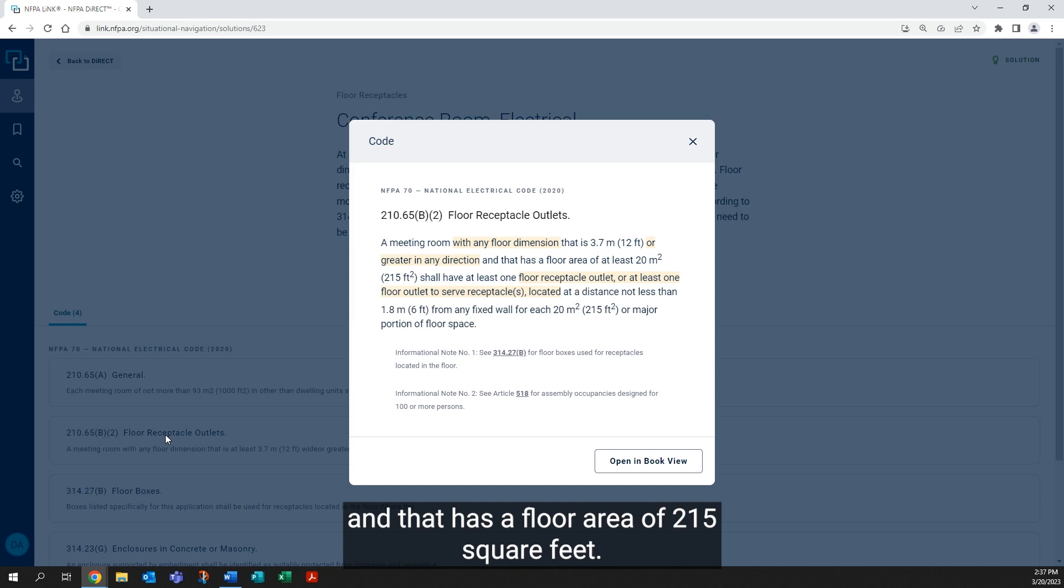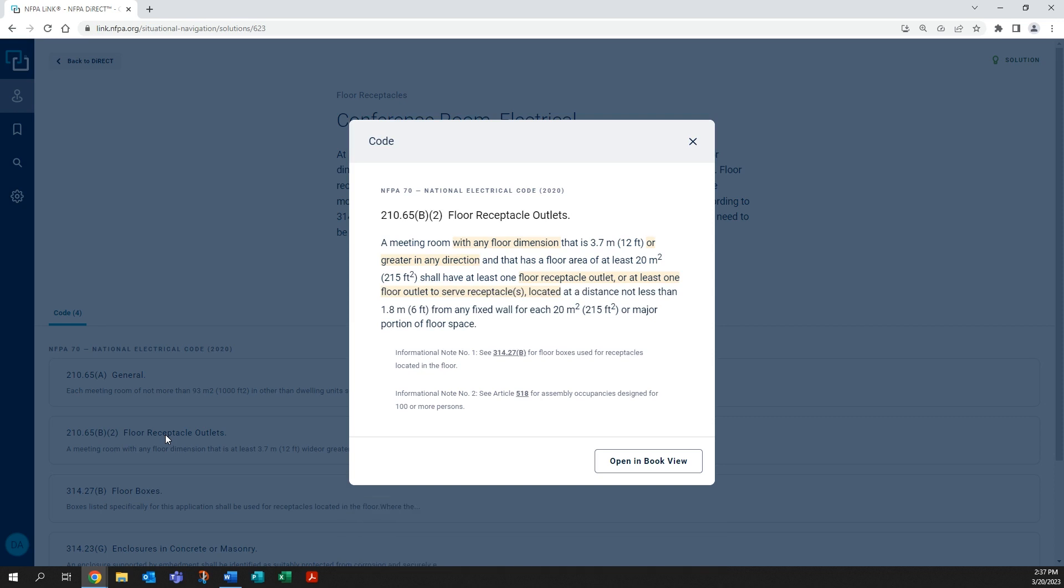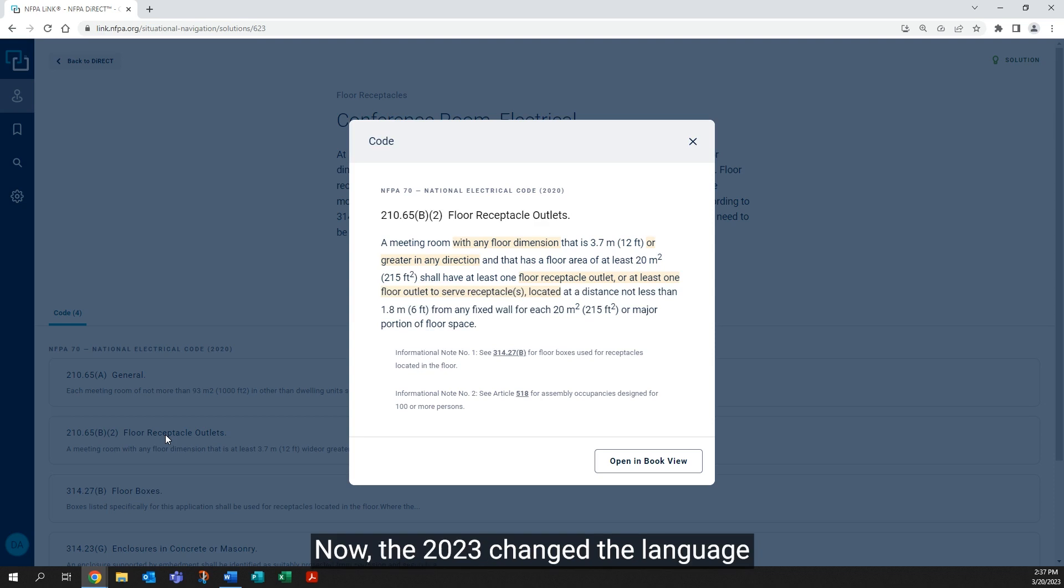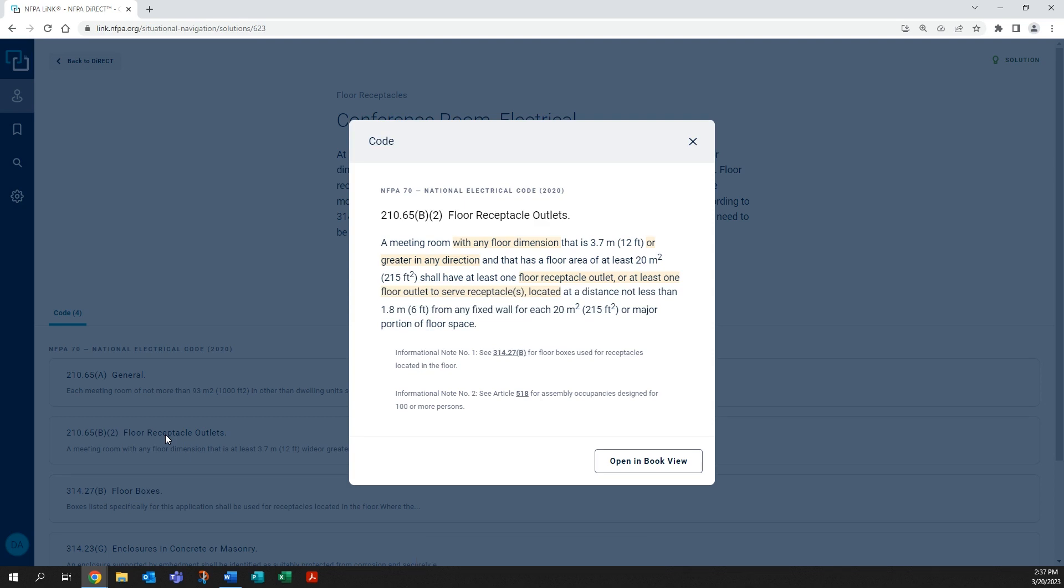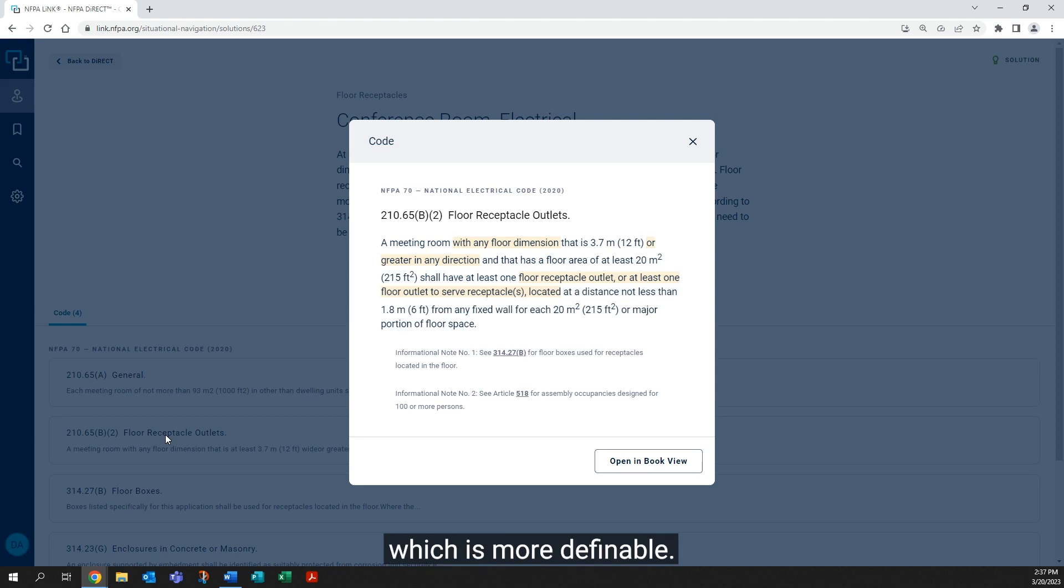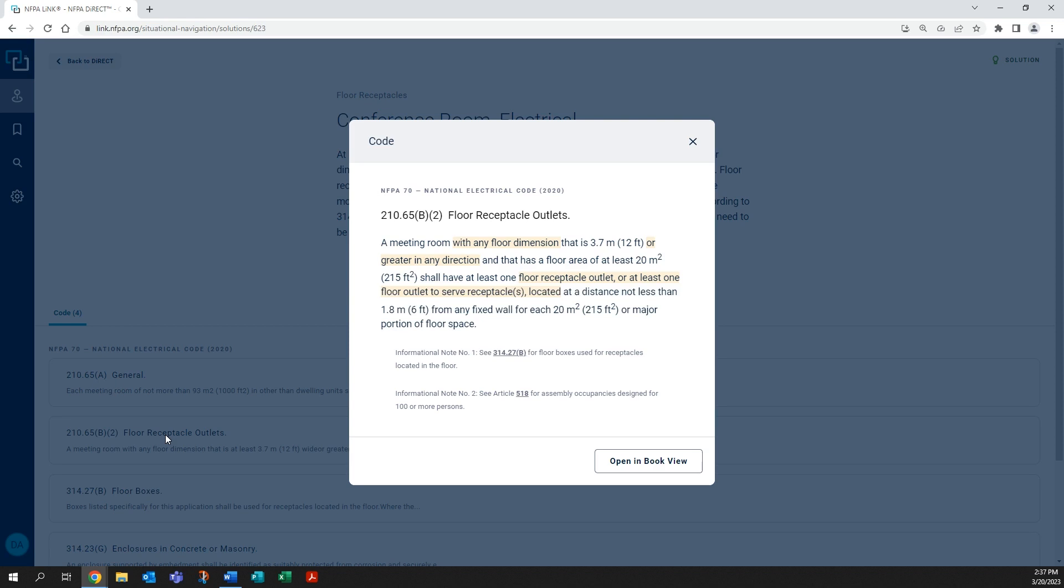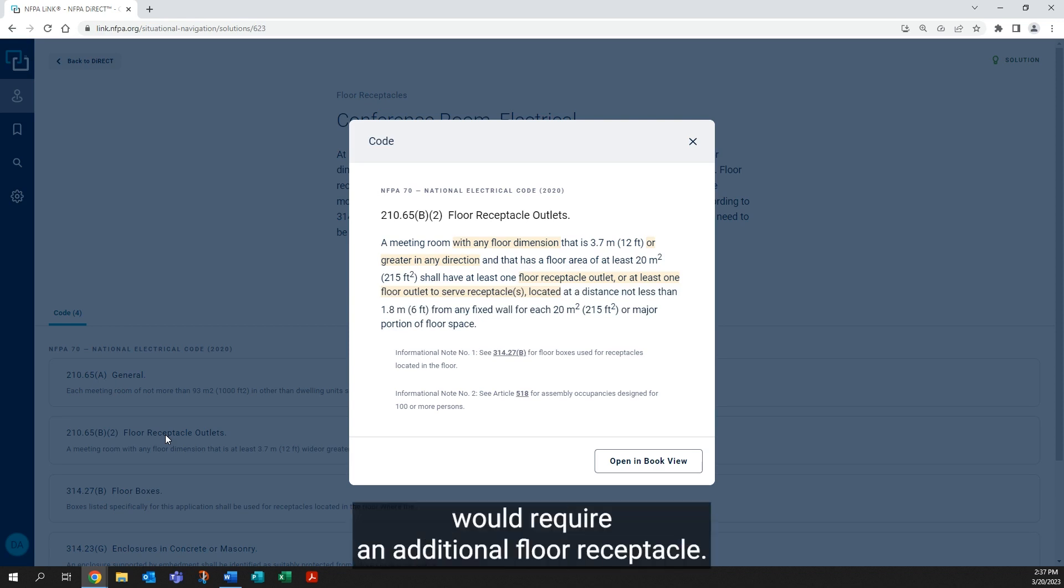Now, the 2023 changed the language from 'major portion' to 'fraction thereof,' which is more definable. So if it's a fraction over 215 square feet, then it would require an additional floor receptacle.